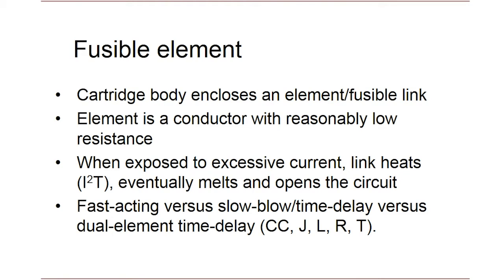Under normal operating conditions, that element has a reasonably low resistance, functioning no differently than any other conductor in the circuit. However, in an abnormal condition, we depend on that sacrificial element to melt or vaporize to clear a fault or overload. Like any conductor, that thermal energy is represented by I²T. If melting occurred in free air, the energy release could be dangerous. So the element is installed within a cartridge body and is usually surrounded by sand to contain and dissipate that energy.